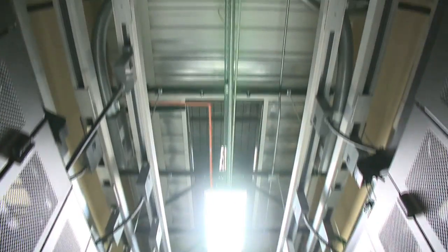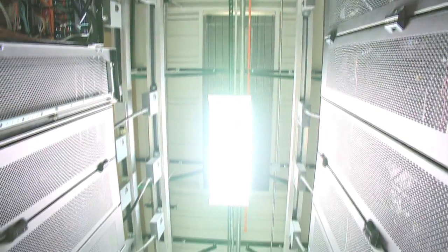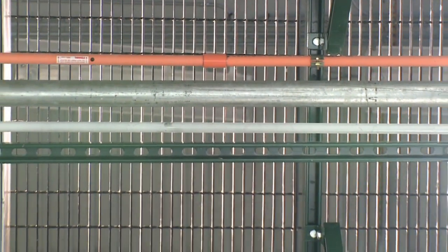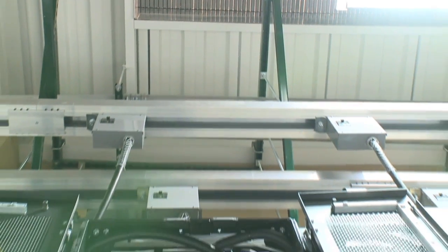As we move over to one of the hot aisles, you can see that both ends are open and that there is no lowered ceiling. As we look up, you can see some of the cable distribution as well as vents or open grates in the ceiling. It is easy to see how the design eliminates the need for ductwork, dramatically reducing fan horsepower and electrical consumption normally required to manage air movement within the data center.